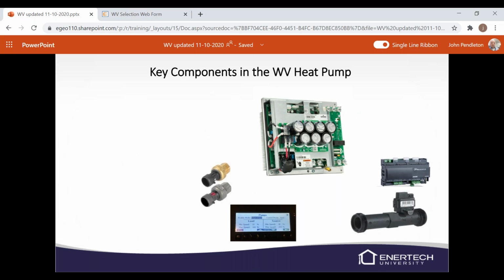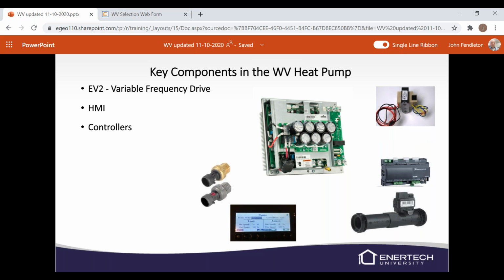The key components of the heat pump. So we have the EV2, that's the big white box with the round, look like capacitors upside down on that. That's the EV2 drive. That's basically what controls the compressor. Tells it what speed it needs to run and throttles it, things like that. HMI, which is in the middle of the screen on the very bottom, that's the human machine interface. We have controllers. We've got an iPro controller, a breakout board controller. We've got flow switches. We've got flow sensors. We've got pressure switches and pressure sensors.